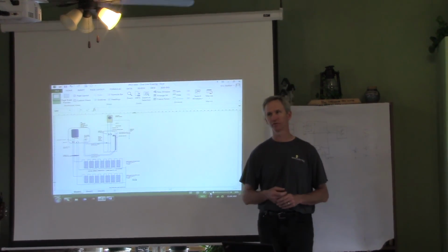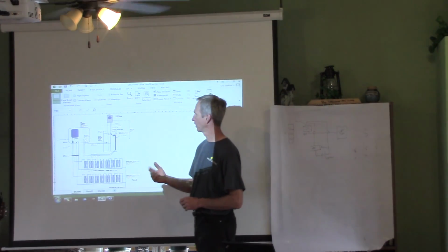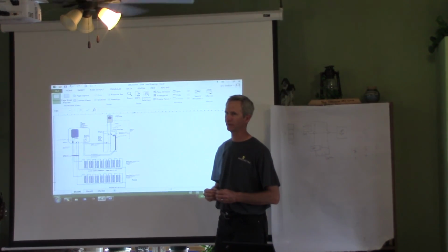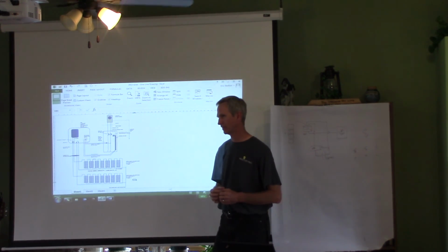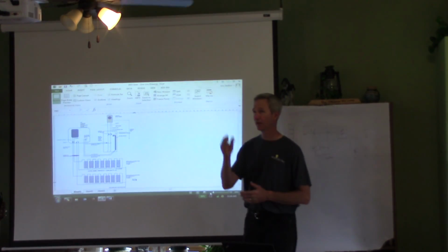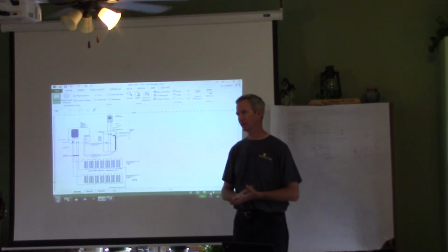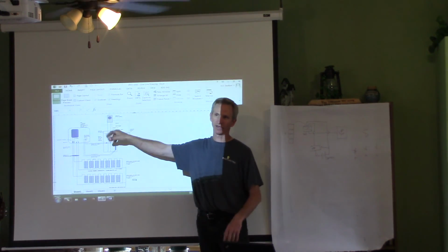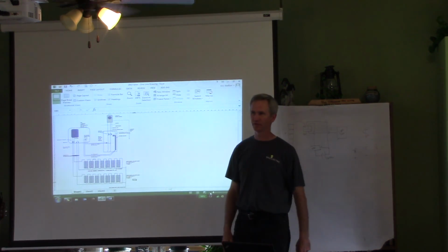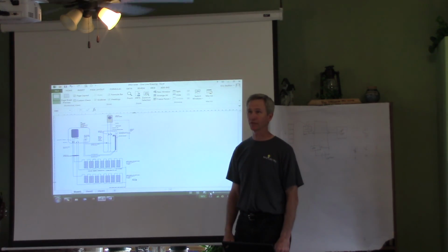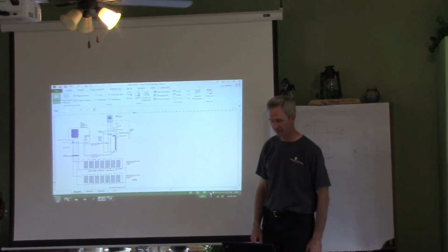Basically, what do you think they would want to do? What would the power company want to test? What would be the big thing that they would want to test? What do you think is the most important thing to them to test at this point? And what do they want to know, Jim? Will it shut down. To do that, they cut the power, they simulate a cut in power, and they want to see the inverter go off. That's it. If they see that, they're happy. They're concerned about their line, yeah, for safety. That's exactly it. That's all we need to do.